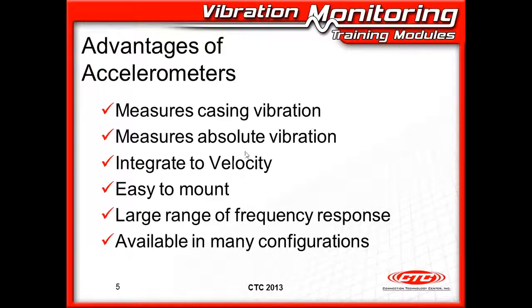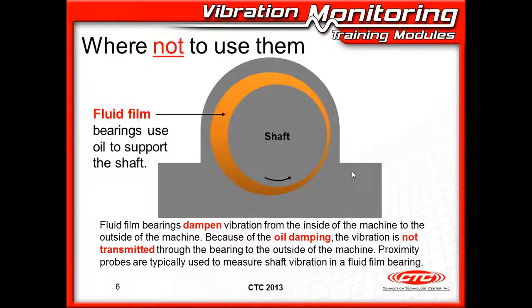What are the advantages of an accelerometer? Well, it measures the casing vibration. It measures the absolute vibration. You can integrate them to velocity. In fact, I would say probably 99% of you are doing that now. You're using an accelerometer in your hand, and you look at your data collector, your condition monitoring system, and you're measuring velocity. They are relatively easy to mount. There is a large range of frequency response, and they do come available in many, many configurations.